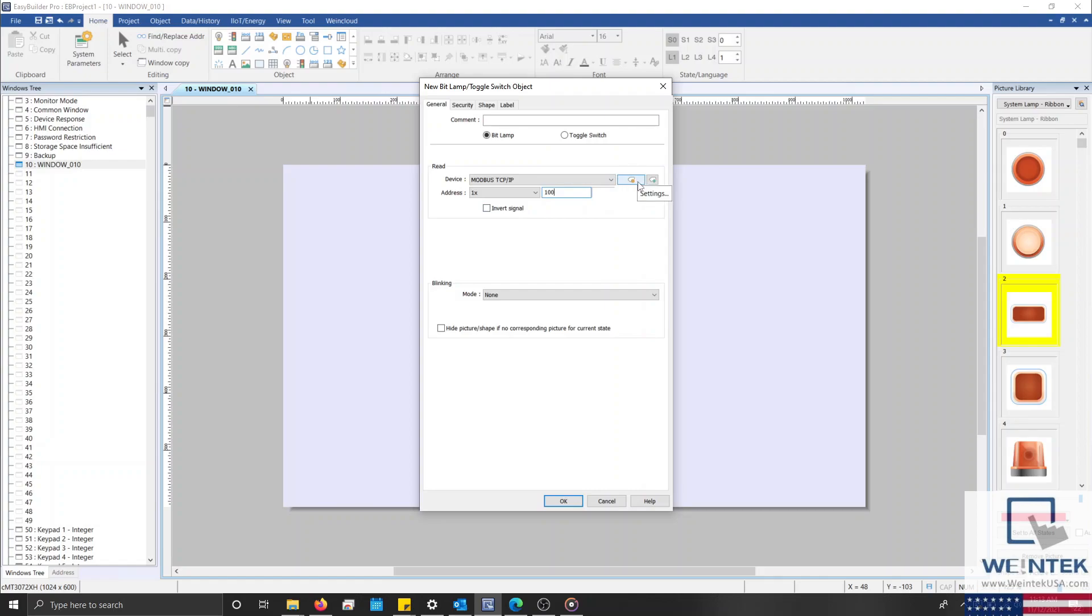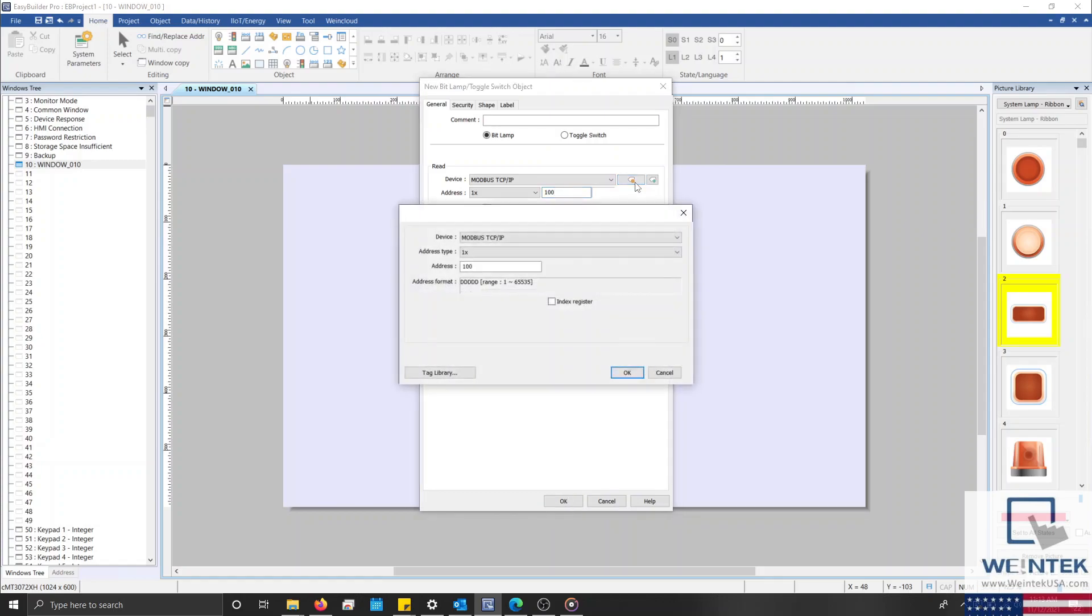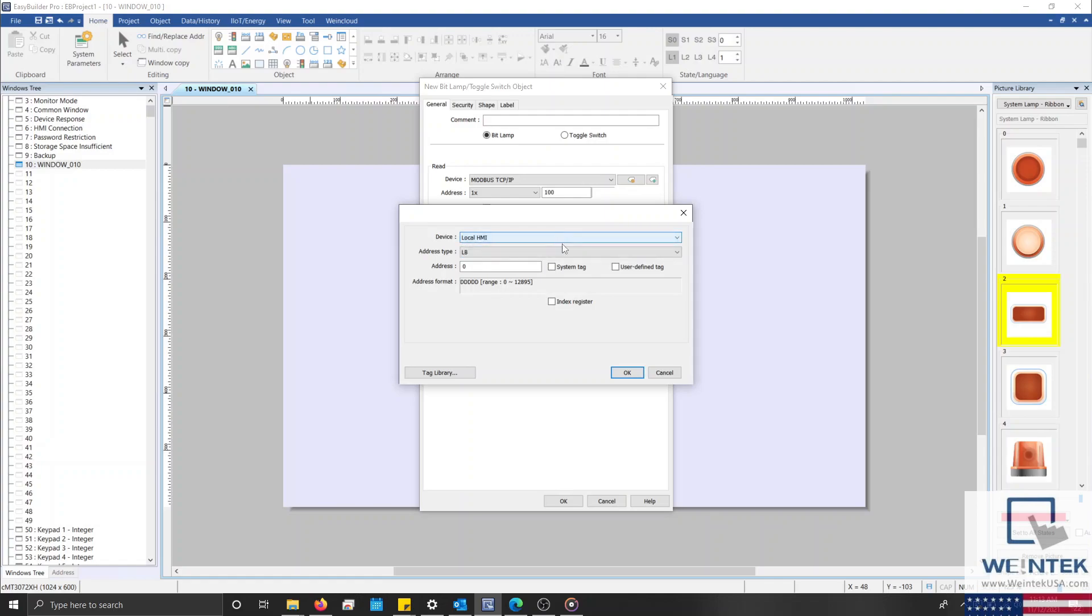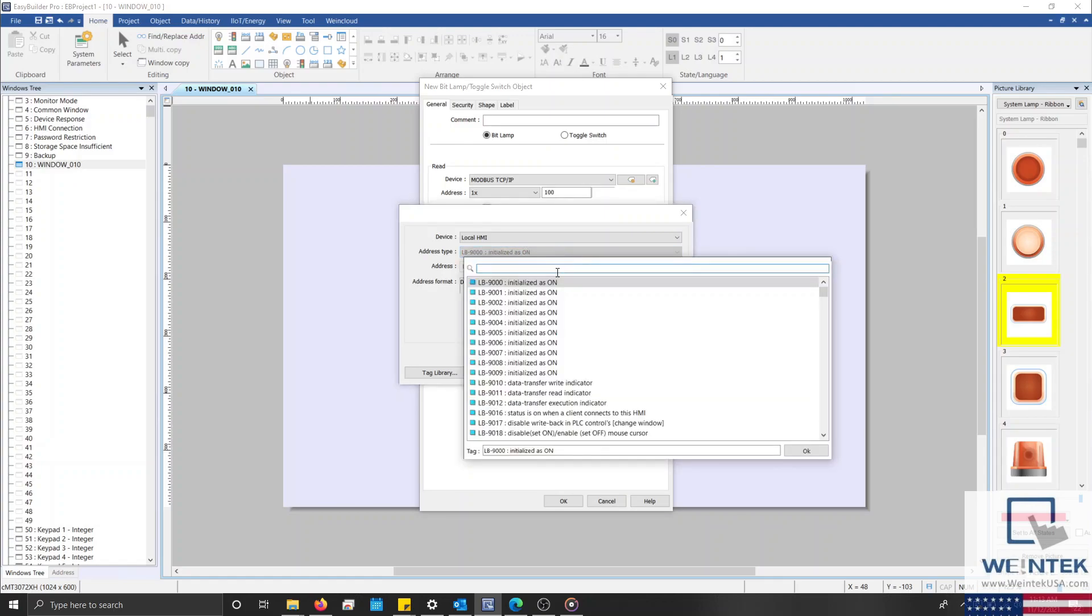To access any of these properties, we'll need to select the Settings button on the right side. Within earlier versions of our software, the Settings button was labeled Settings. However, within the current version, the Settings button now depicts a tag with an orange dot. I'll select this button, and within the following menu, we can access our system tags by specifying the device as our local HMI. With that configured, I'll select the System Tag checkbox below, which will allow us to quickly search for and access system tags applicable to our device that write to or read from certain internal functions within the HMI.